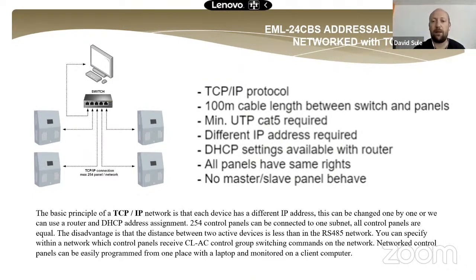you can mix the two types of communication between the panels. So between the buildings, you can use RS485 networking because the cable length can be 1,200 meters. But inside the building, you can use a TCP/IP network.